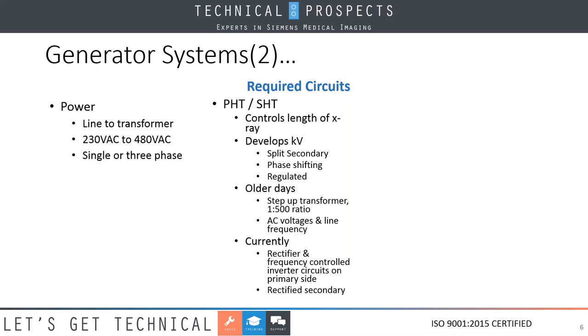These circuits actually control the length of the X-ray, but this is also where we develop the kilovoltage. Here we use the split secondary, we use phase shifting, and we regulate the output of our KV. In our older systems, we basically used a 1 to 500 ratio step-up transformer that was subject to AC voltages, our incoming voltage, and also line frequency of either 50 or 60 hertz, depending where you are in the world.